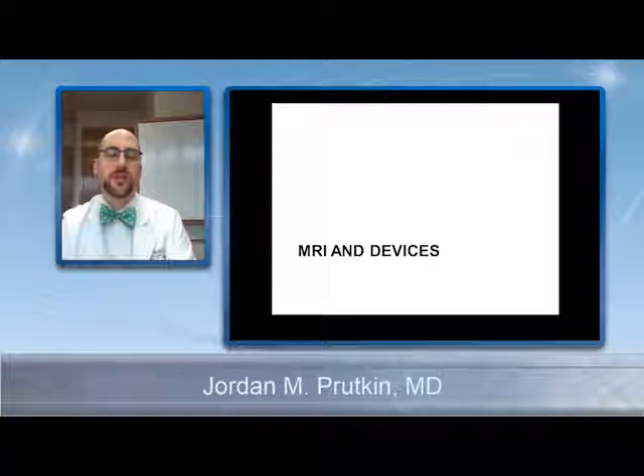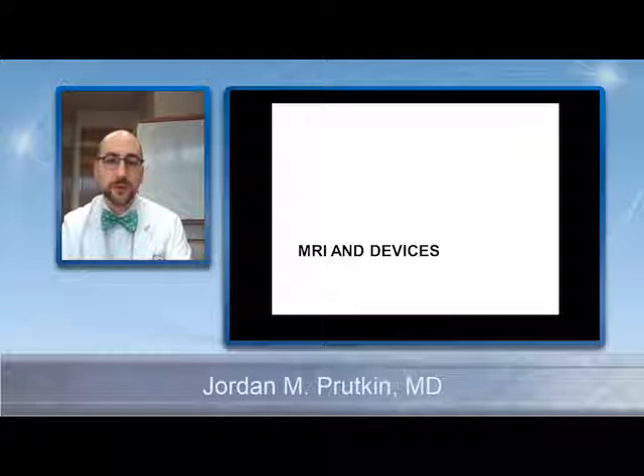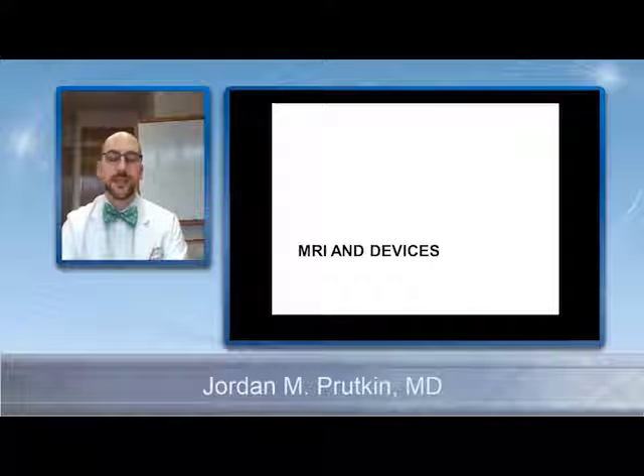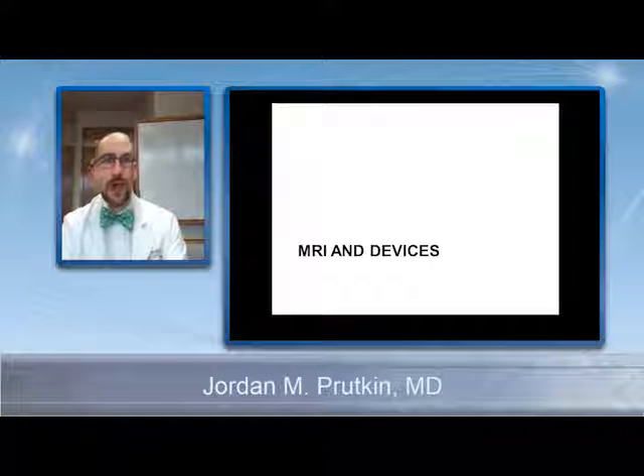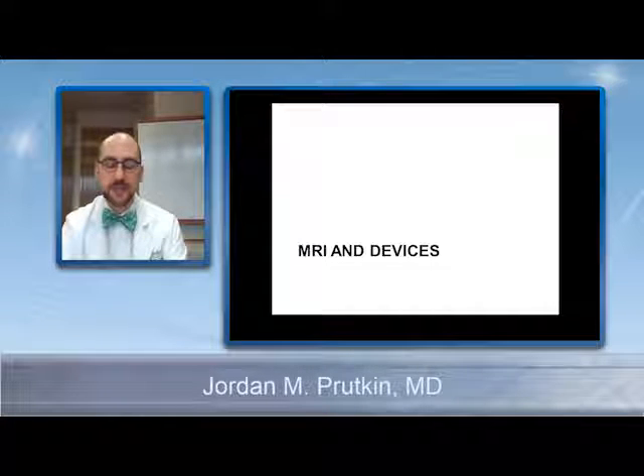MRIs and devices. So there are some new developments in the last few years having to do with MRIs. Some of this you might know, and some of this you may not know. In terms of pacemakers and ICDs, there are now several different types of MRI conditional devices, or FDA-approved MRI conditional devices. So each of the manufacturers now makes a pacemaker with leads that you're allowed to get an MRI for if the pacemaker is checked right beforehand, the patient undergoes the MRI, and then the device is checked right afterwards.